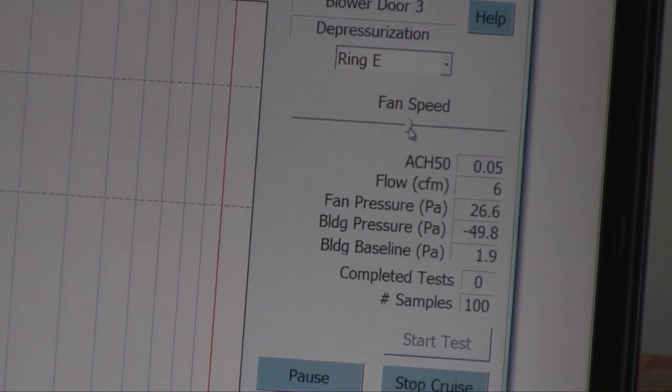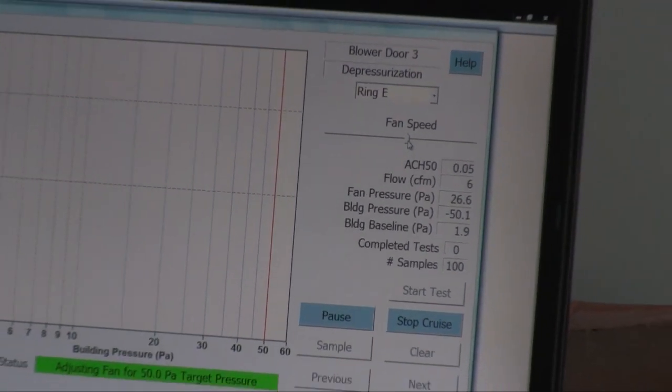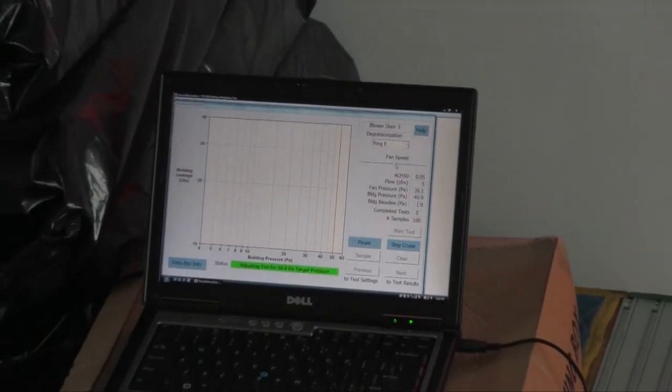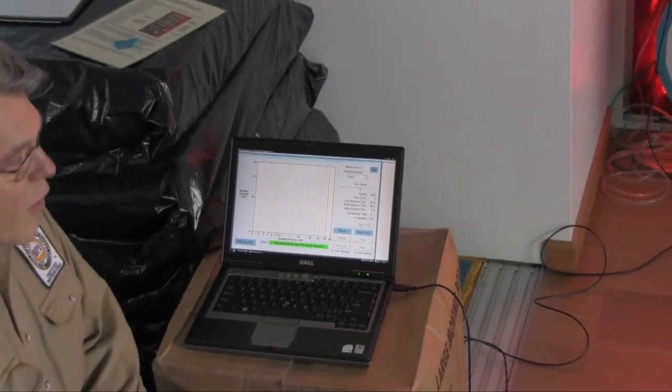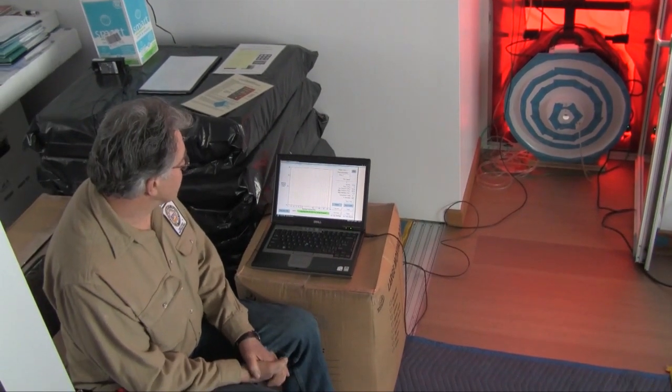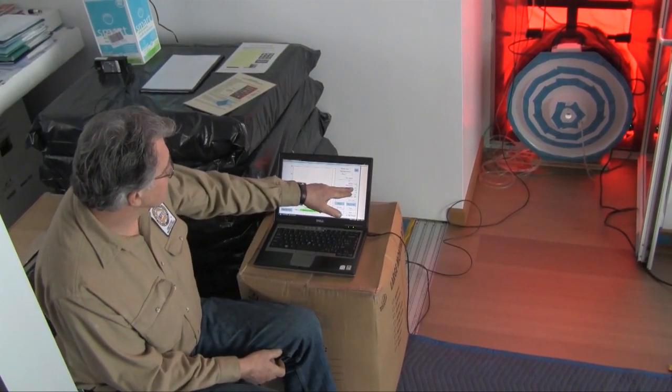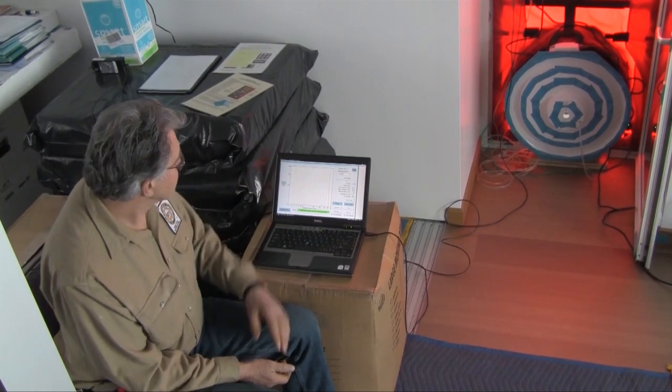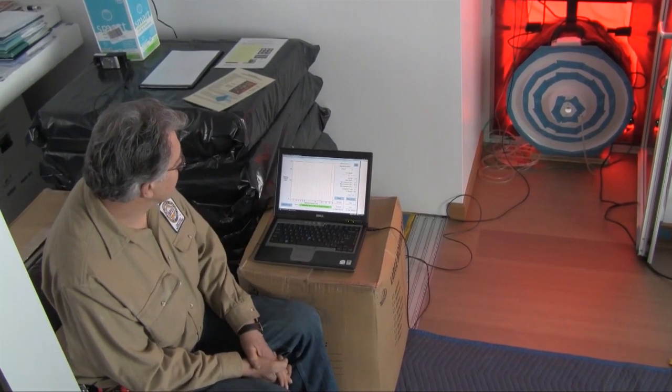We've been doing some practice tests here. That's about where it's been hanging between 4 or 5 or 6 cubic feet per minute to maintain 50 pascals. And it's still doing exactly that. It's at 5 cubic feet per minute at 50 pascals right now.